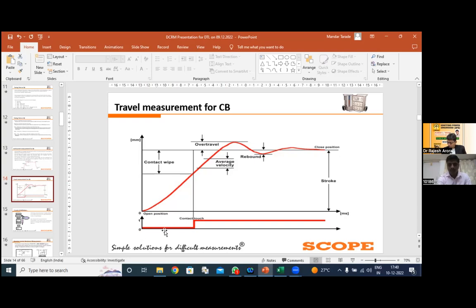Here, if you see on my screen, I have taken the timing graph where the change in the contact happens. From the 0 to the first touch is your contact gap. The value of the contact gap is there in my consecutive slides. Moving further, the delta between the first touch and the travel stabilization point is your contact wipe. The summation of the contact gap plus the contact wipe will give you the idea about the total travel of this CB. If you place the cursor at the 0th position where your mechanism is idle, with no movement, and at the second position where your mechanism has rested after performing the operation, the delta between these 2 points will give you the total travel.